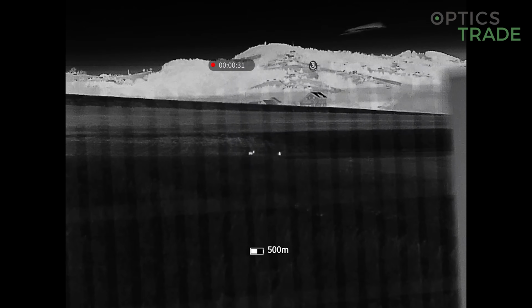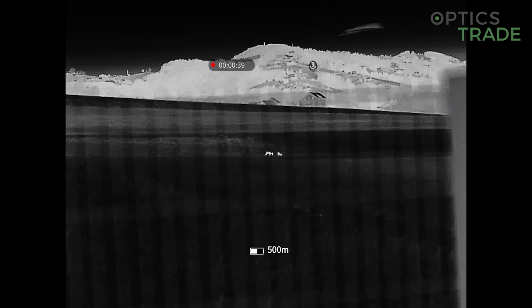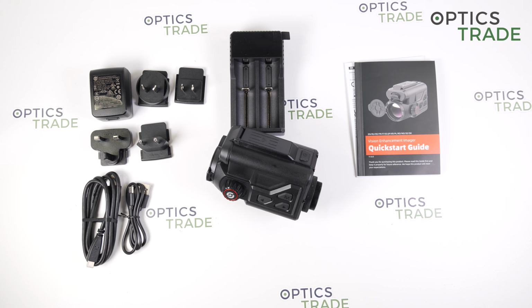It has two calibration modes: automatic, where the time when the device will start to calibrate is shown on the screen, so you immediately see it. If you want to make the shot and the timer is running, it's better to stop and wait for the calibration, and after that make the shot placement. Or you can adjust it to manual, which I personally prefer for clip-on devices, because then you can make the calibration whenever you want or you see some image degradation.